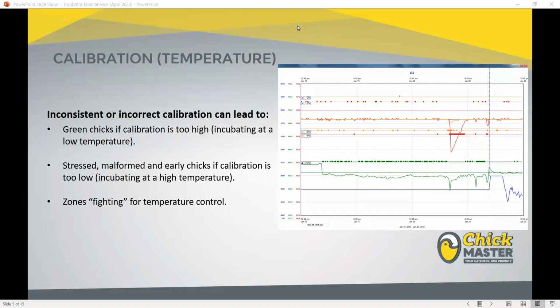Now the graph on the right-hand side of this page is indicative of what you'd see in a setter with the calibration offset being too low. At the very top of this graph, you can see the cooling load for zone 1 on the red line and zone 2 on the orange line. So this is right at the top of the graph. I'm looking just up here. These two lines just here.